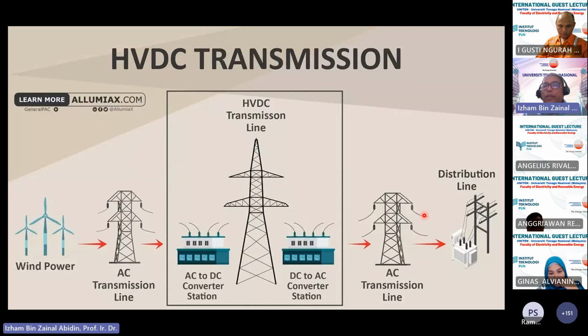Now, typically HVDC is very good when I want to protect the network from another network. In Malaysia, we only have an HVDC line from Semenanjung, Malaysia to Thailand. But from Semenanjung, Malaysia to Singapore, we have a direct line connection. The reason is that we want to isolate the Malaysian network from the Thailand network so that any issues in Thailand will not be transferred into Malaysia. In the US, for example, they have multiple DC systems to protect small parts of their transmission network. In Indonesia, do you have a lot of DC transmission lines, or is it all AC?